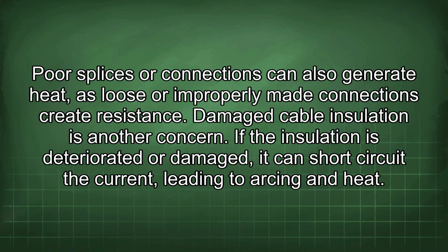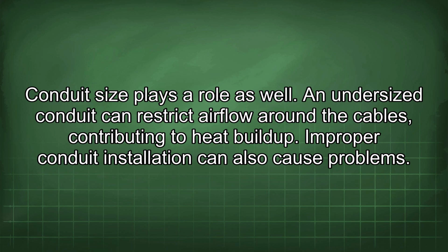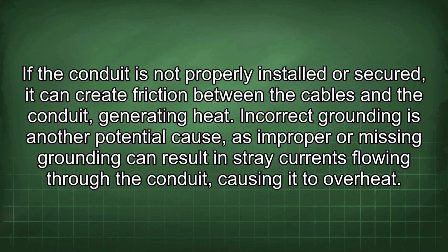Damaged cable insulation is another concern. If the insulation is deteriorated or damaged, it can short-circuit the current, leading to arcing and heat. Conduit size plays a role as well. An undersized conduit can restrict airflow around the cables, contributing to heat buildup. Improper conduit installation can also cause problems.